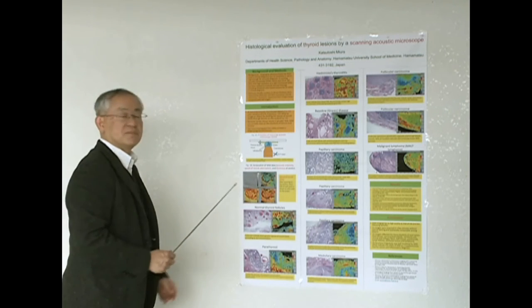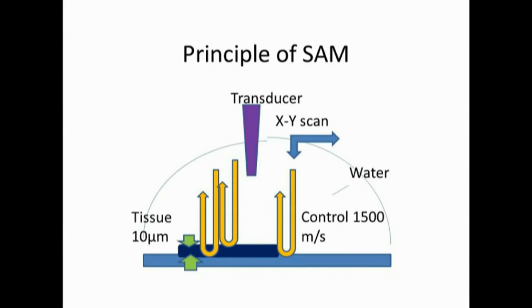This is the principle of this microscope. Ultrasound from the transducer reflects off both the glass slide and section, and returns to the transducer. These waves pass through 10 micrometer sections. The transducer automatically scans the section to calculate the speed of sound through each area.